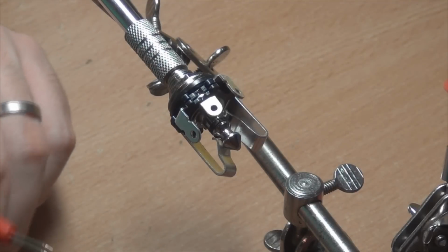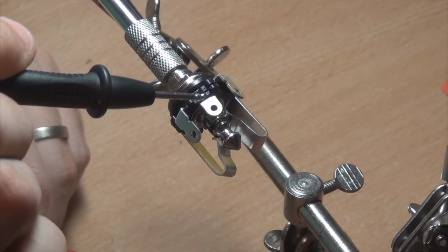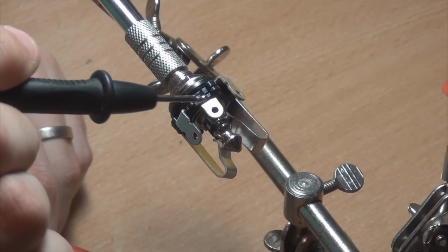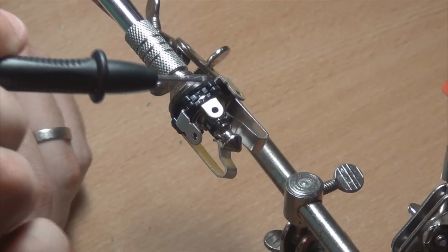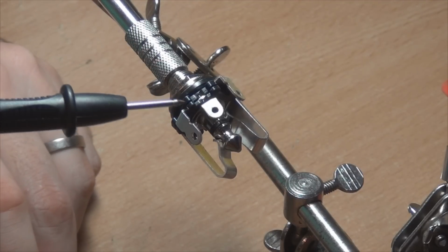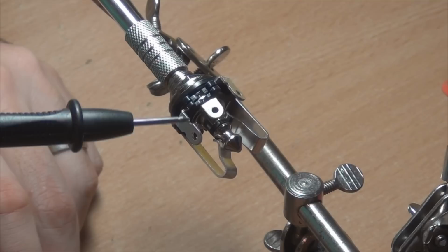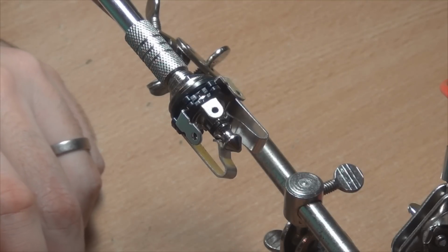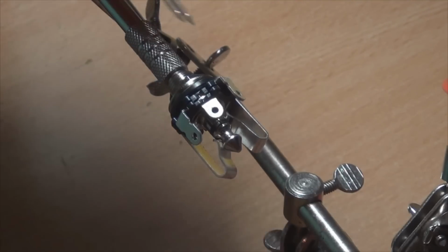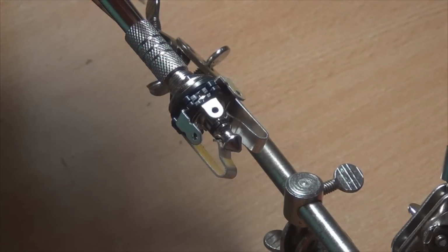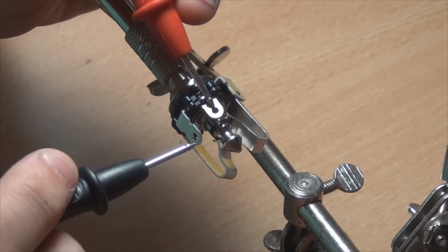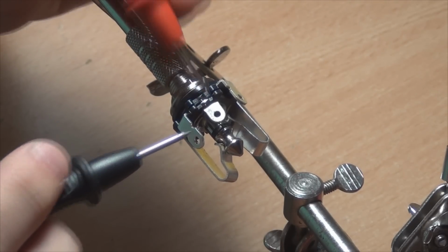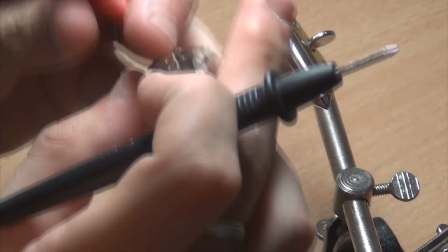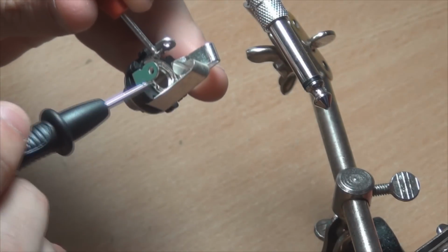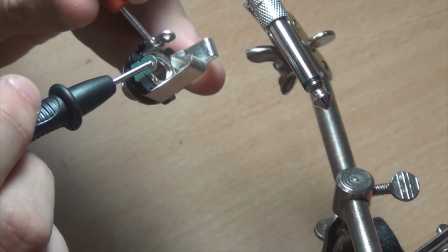Basically how that works: you'll have the negative of your battery connected to the ring lug, and ground connected to this lug, which actually goes through the enclosure. So now if we test it, there's a connection between those two. If I pull that cable out and test it now, there's no connection between the two.